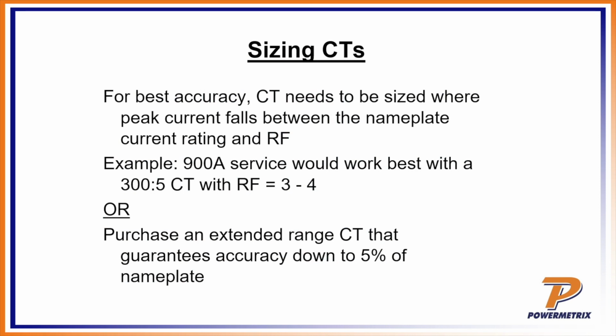And you can also get an extended range CT. So let's talk about that for a second. So I got the rating factor of, let's just say 4 on the 300 to 5. So I can go all the way up to 1,200 amps on the 300 to 5 with a rating factor of 4. But when I get the extended range CT, that goes the other way, down to the low end.